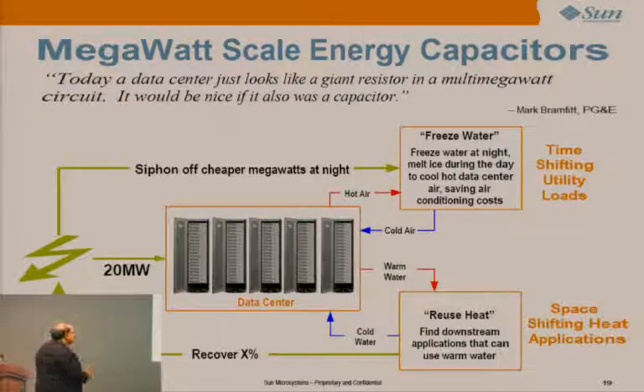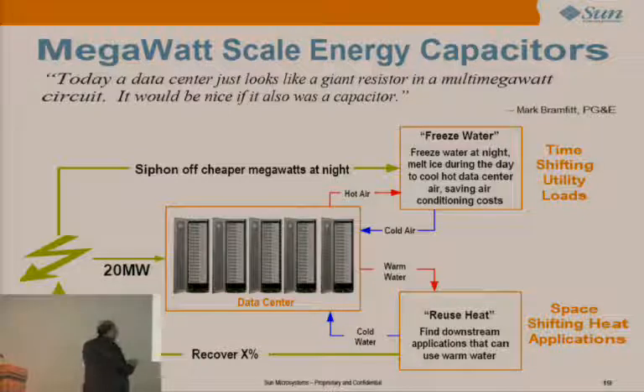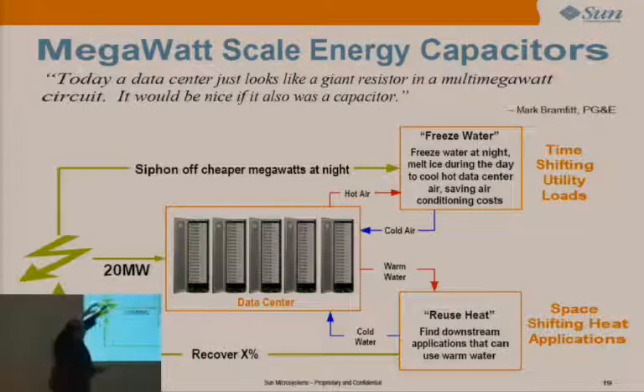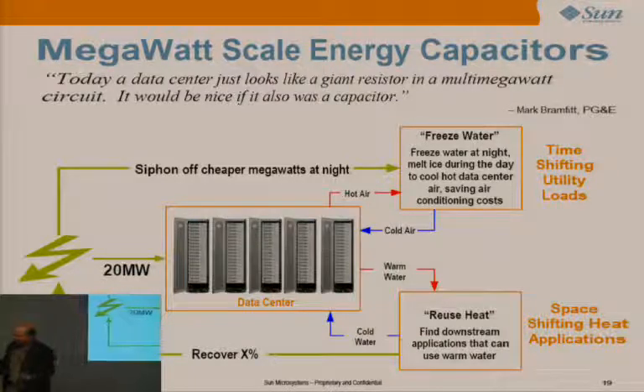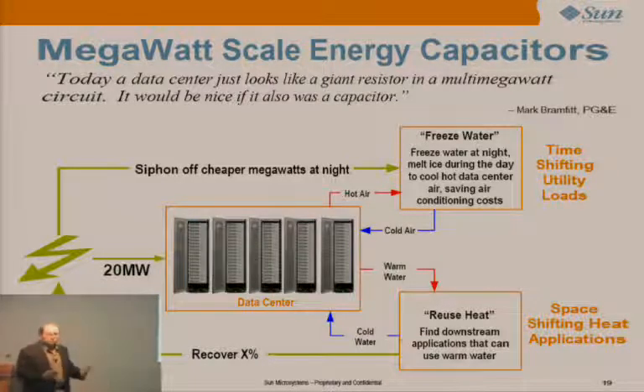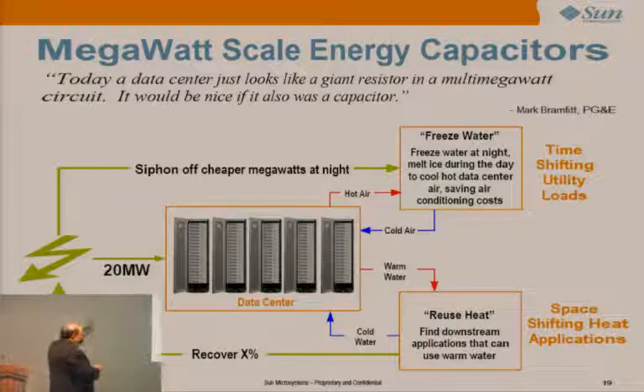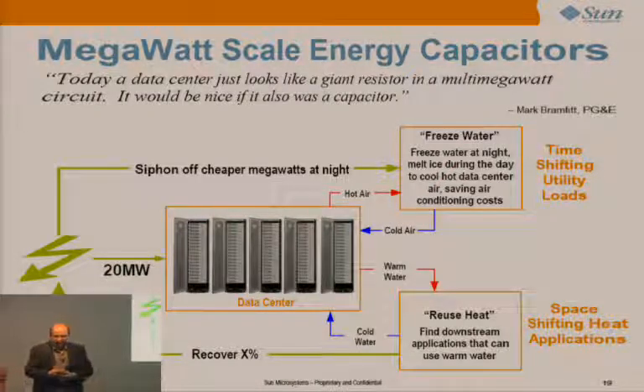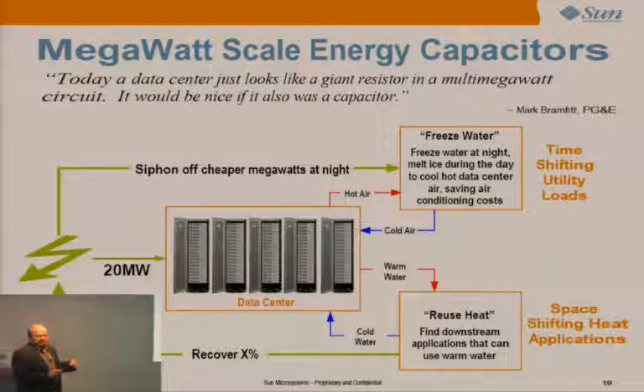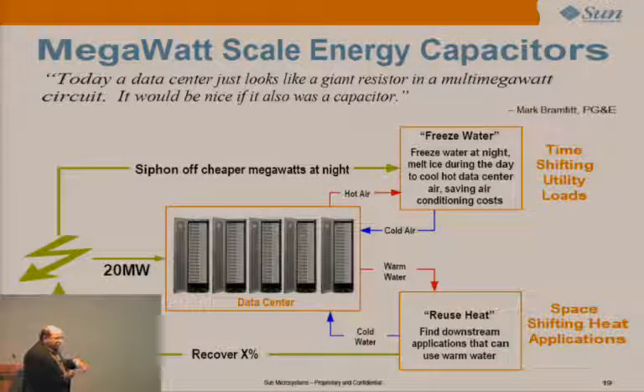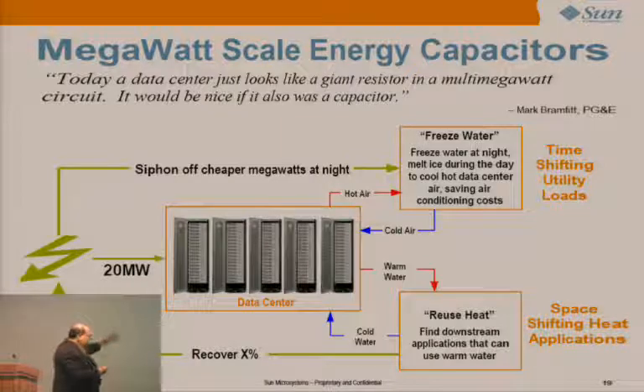So what some data centers are beginning to do is siphon off the cheaper megawatts at night and create a form of stored energy. It's very expensive to store energy - you can't do it in batteries because it's very capital intensive. What these people are doing is freezing water using cheap electricity. Then during the daytime, they don't actually power up the air conditioners - all they do is convect air over the ice blocks, and then they get cold air that they pump into the data center. So they save money that way.